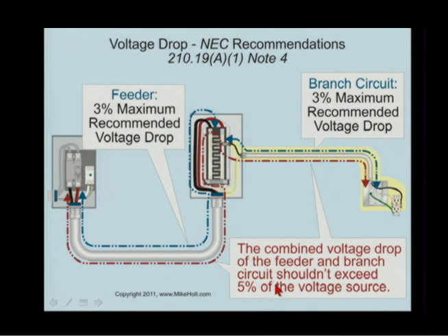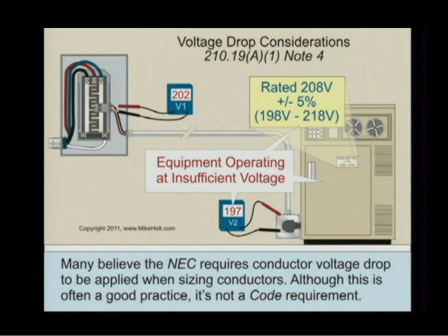Steve? I think on that last one, Mike, we actually were rounding the wrong way. If we round 0.6, we actually were a couple tenths of a volt too low on that. Say that again to me here. We came up with 197.6, and we're supposed to have 197.6 or more. So if we actually have 197, we're 6 tenths of a volt low. Oh, you're saying that if the minimum at 5% was 197.6, we rounded to 198 in that top. Well, even if we did round it off, if the minimum was supposed to be 197.6, this is actually below the 5%. Yeah, we're just a little bit low on that.